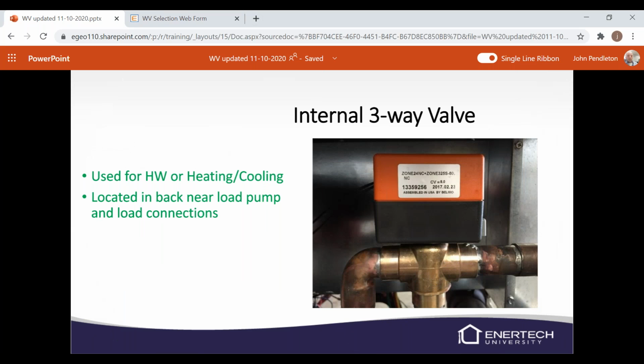This is the internal three-way valve, and it's used for shifting from hot water to heating and cooling. When you're flushing, it'll go through the setup wizard, and you'll have to move this valve into the hot water position so we can flush the hot water circuit as well. It is located in the back near the load pump and the load connections. If it has to be replaced, you're going to have to take the top off the unit. You can remove just the head on it. If for some reason the head fails, it can be replaced by itself.